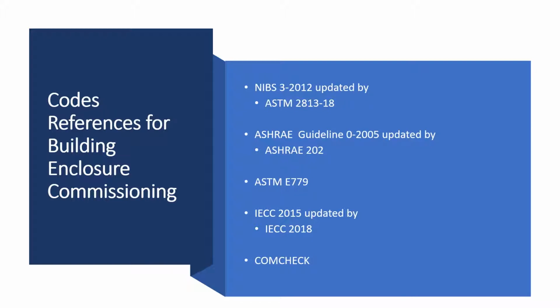As we delve into this, let's get a little background about the codes that reference building enclosure commissioning. We'll be talking about these. One is NIBS 3-2012. It's since been updated with an ASTM standard. ASHRAE Guideline 0, which has also been updated by a newer standard, ASTM E779, and IECC 2015, which we're going to refer to throughout this presentation, because that's the code under which these projects were designed and permitted. However, now the IECC 2018 has been accepted by many jurisdictions. And then finally, ComCheck.